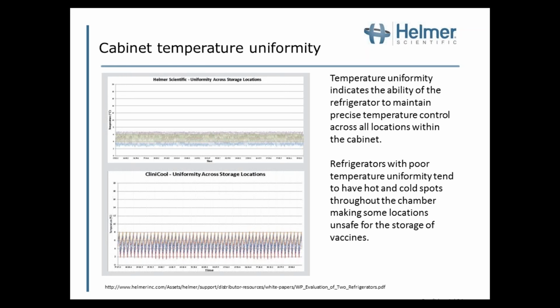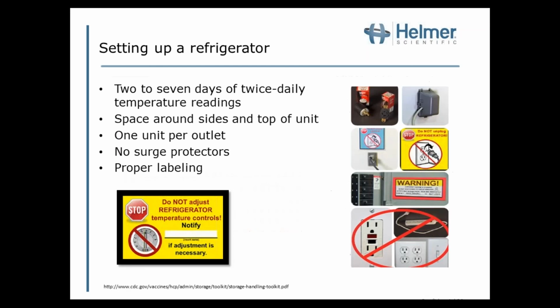Even with purpose-built refrigerators and freezers, there can still be some difference in temperature uniformity. The recommendation for pharmacy refrigerators is to keep temperatures within 1.5 degrees Fahrenheit, depending on where you are. I'd encourage you, before buying a unit, to ask the manufacturer for data on temperature uniformity to make sure they have evidence to support what they claim the unit can do.